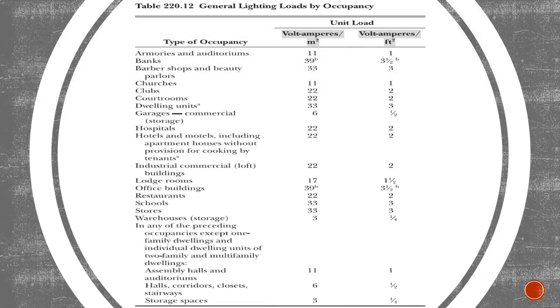Step one: our general lighting load. We're going to Table 220.12, take the square footage of our building and multiply it by our volt-amp amount. The only thing to keep in mind is that this is specific to the type of occupancy. Since we're doing a warehouse, we go down that column to 'warehouse for storage' and across to see one-quarter volt-amp per square foot, which is much less than our dwelling unit was. So for step one: 10,000 times 0.25 equals 2,500 volt-amps.